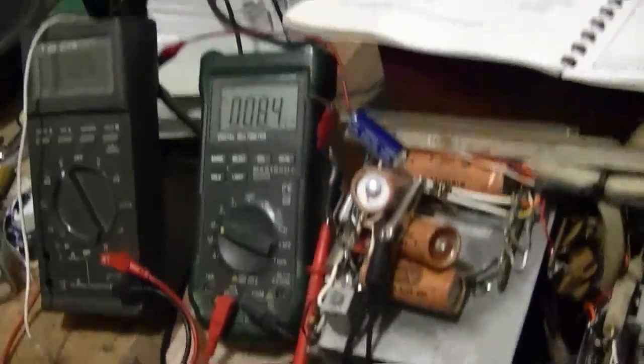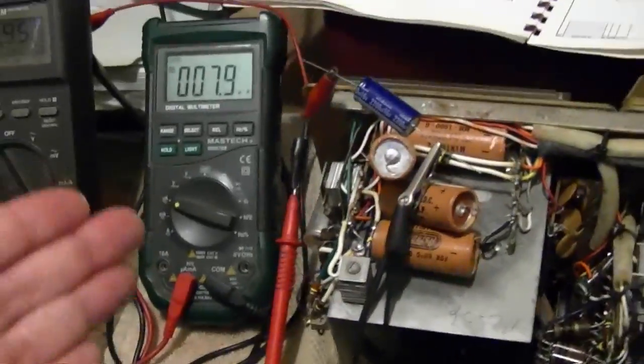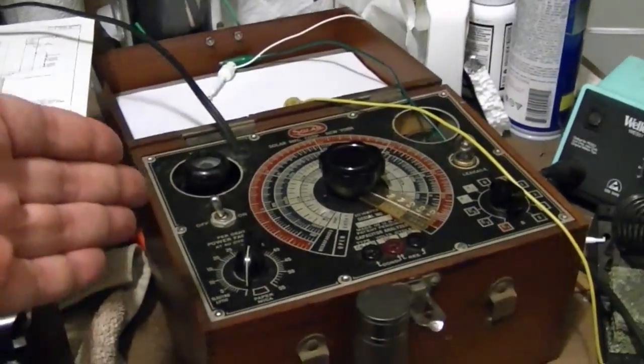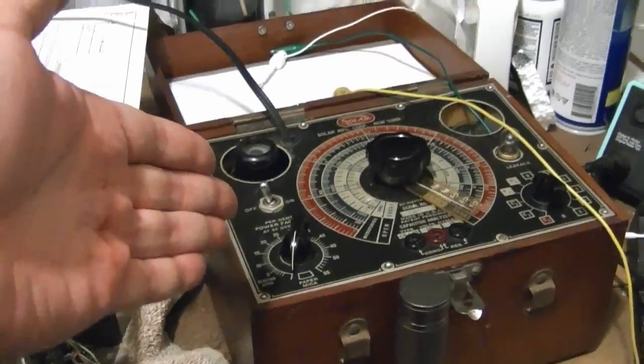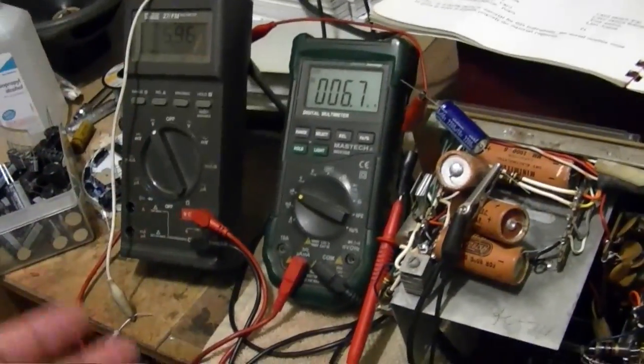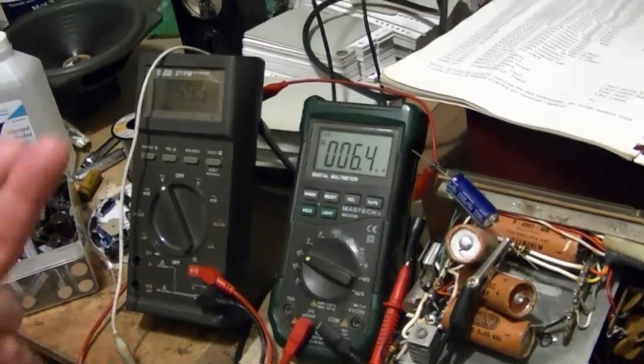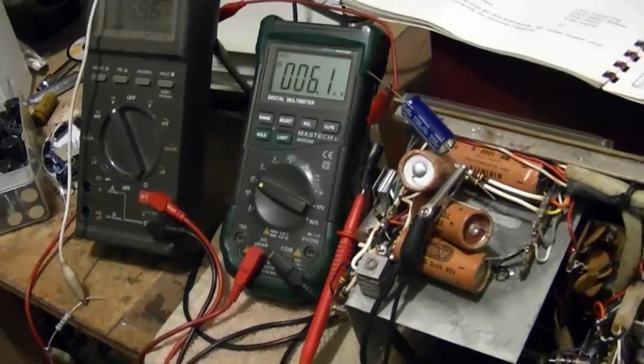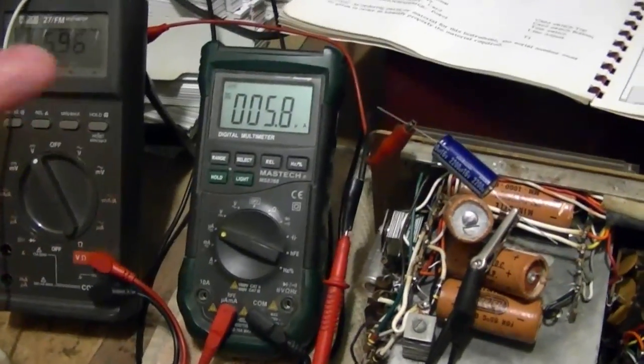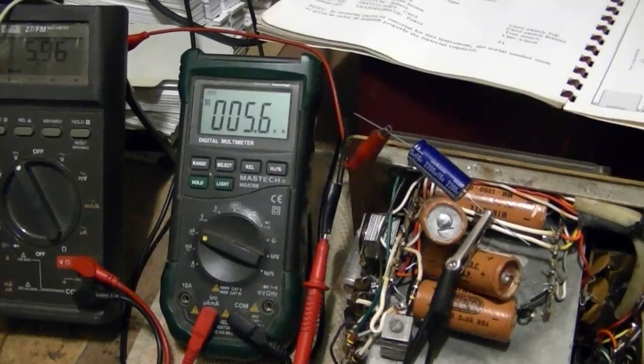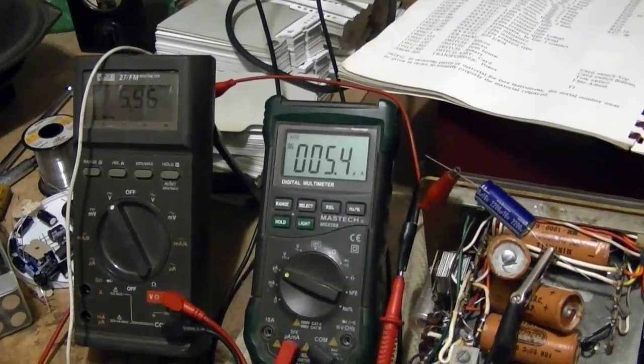So, if you have the time and the patience and you want to check for leakage in old caps, and you don't have something like this, or it's outside the range of this, you can rig something up like this if you've got a couple meters lying around and a DC power supply. Just measure the leakage current in the cap with a DC voltage applied to it.